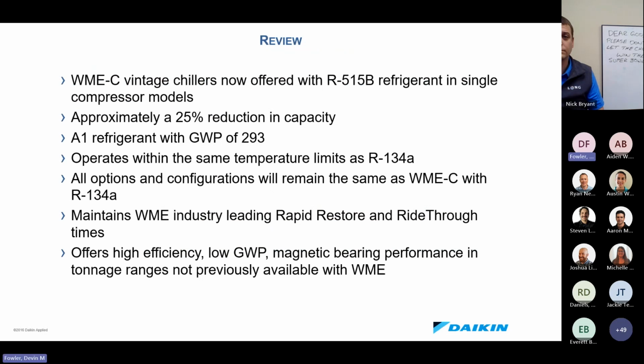So in review, WME C Vintage is now offered with R515B refrigerant, single compressor models only at this time. We will have dual compressor models available later. Approximately a 25% reduction in capacity when going from R134A to R515B. We will still remain as an A1 refrigerant, but we're able to lower that GWP down to 293, giving you another option for a low GWP replacement for R134A. We'll operate within the same temperature limits as R134A.